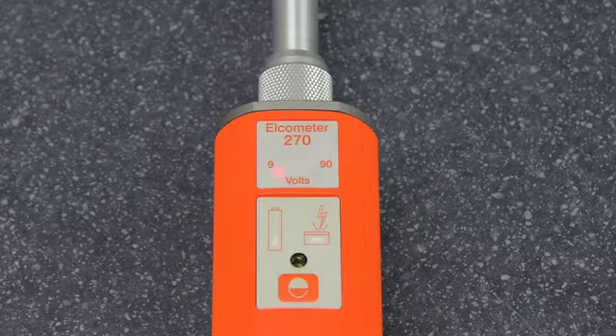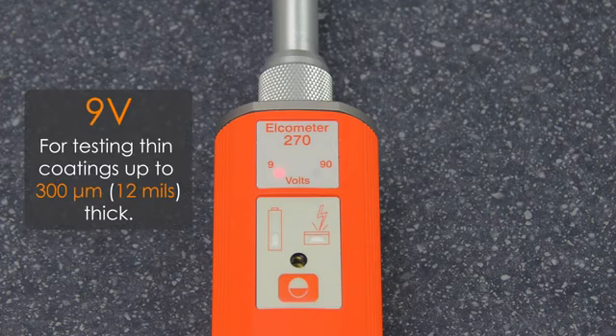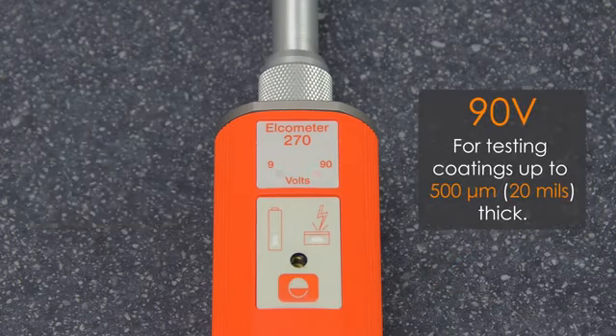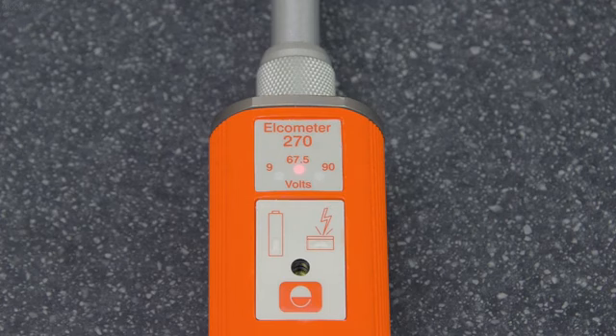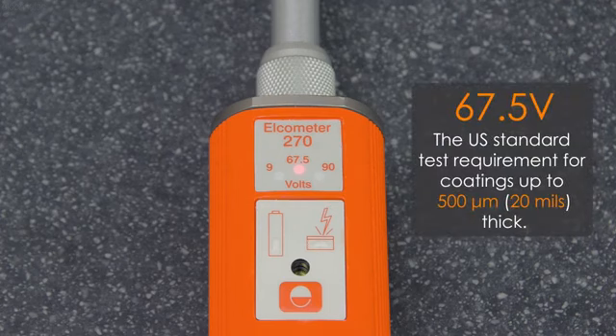The Elcometer 270 is available in either dual or triple voltage models. The dual voltage model can be set to 9 volts for testing thin coatings up to 300 microns or 12 mils thick, and 90 volts for coatings up to 500 microns or 20 mils thick. The triple voltage model can also test at 67.5 volts, the US standard test requirement.